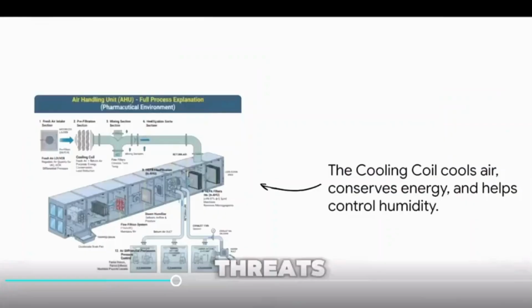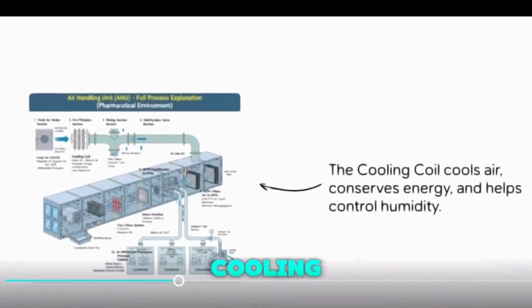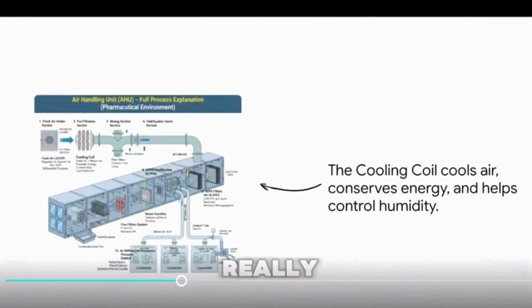Right after that, it passes over the cooling coil. This part is really clever because it does two crucial things at once. First, it cools the air down to the perfect temperature, but it also helps save a ton of energy by pre-cooling some of the air that gets recirculated. It's this brilliant piece of efficiency that also helps control humidity.